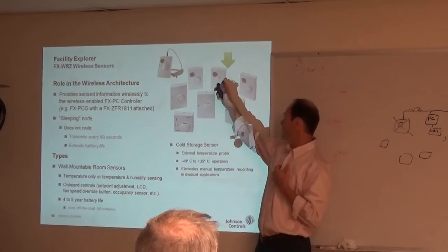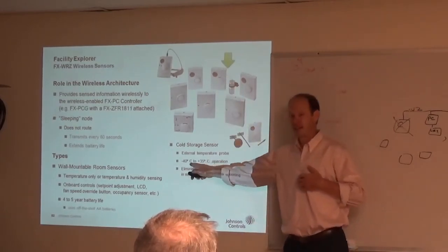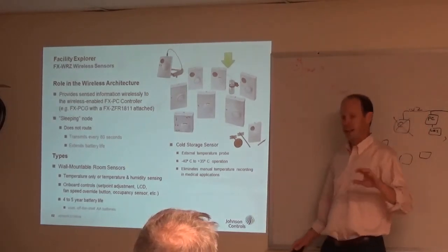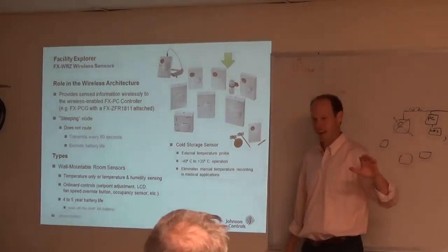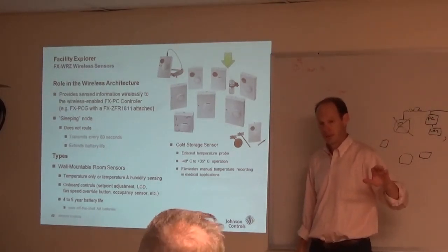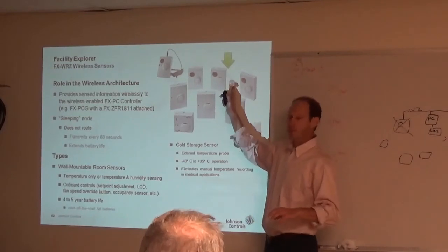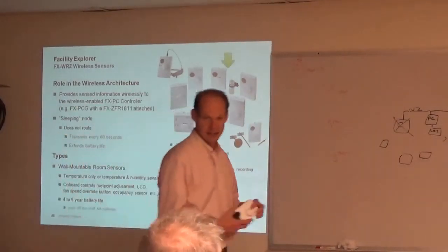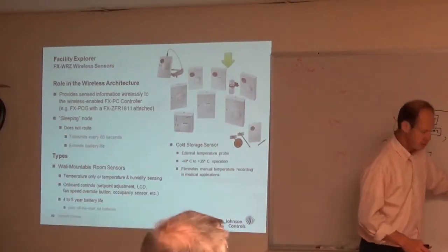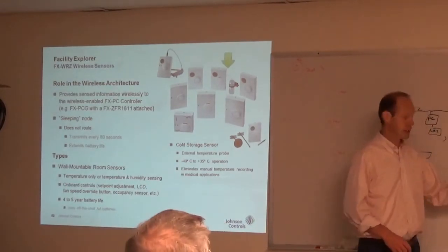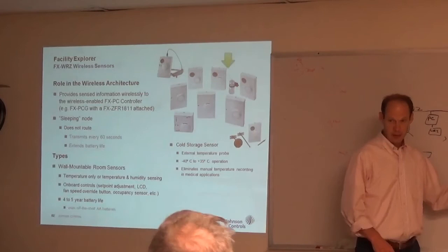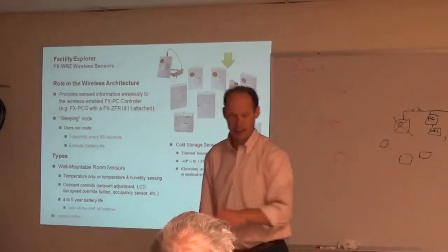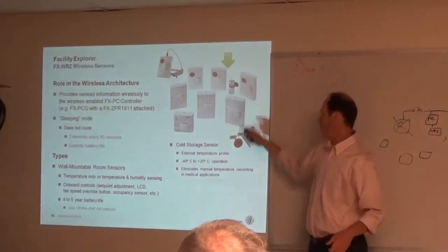The cold storage sensor, this guy right here, to be able to do those temperatures, negative 40 is the lowest we go. I don't know if that's low enough. Maybe Eli Lilly might go to like negative 80. The electronics is not negative 40. No, the sensor is. Yeah, the sensor, that's the big problem. The electronics is mounted on the outside of the box. It's not meant for outdoors, this is indoor stuff. But that mounts on the outside, and then the wire goes across the seal and is mounted in the box, right?